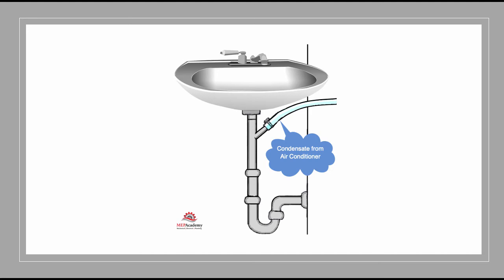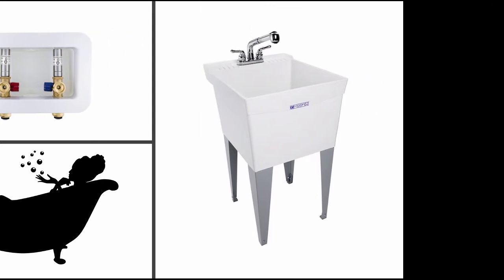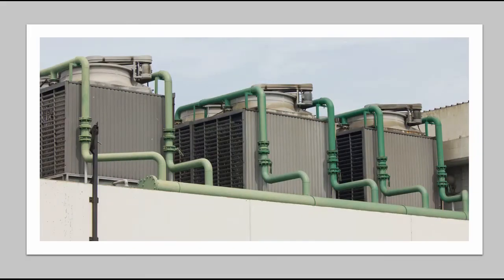If you go to an indirect drain, the choices are a lavatory tailpiece in the same tenant space as the air conditioner — it needs to be in the same location and same tenant as the air conditioning cooling coil. You can also go to a laundry standpipe, janitor sink, or the inlet of a bathtub overflow, but it must be accessible. In some jurisdictions, due to water conservation requirements, they want you to collect the condensate and send it to the cooling tower to recirculate it back. Check your local code.